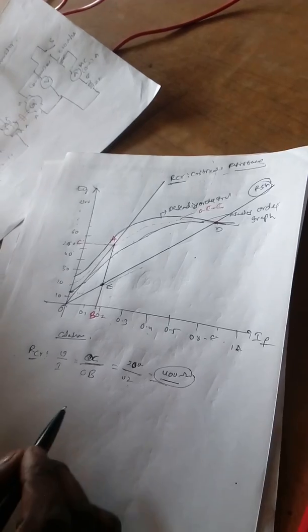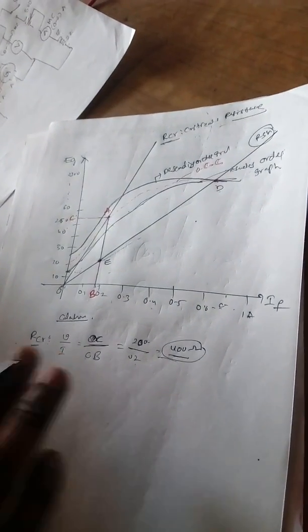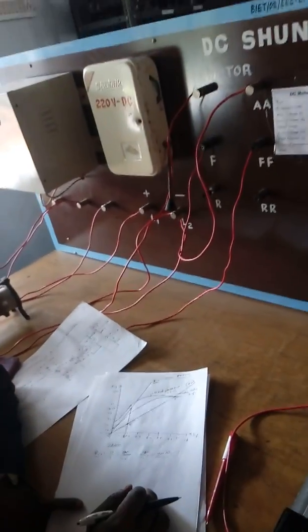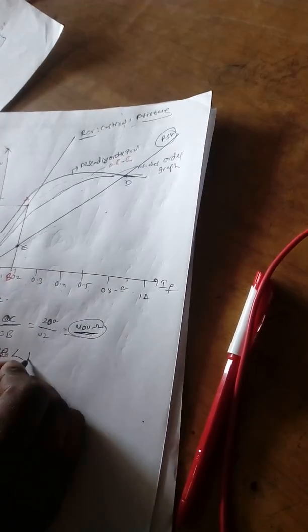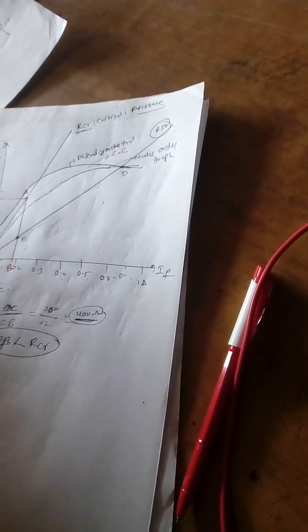What is meant by critical field resistance? This is the resistance above which the generator fails to build up the generated voltage. So you need to operate with a field resistance RF that is less than the critical field resistance. Then only the generator will generate some voltage — above that value it cannot. For example, if the field resistance is more than 400 ohms, the generator will not generate voltage.